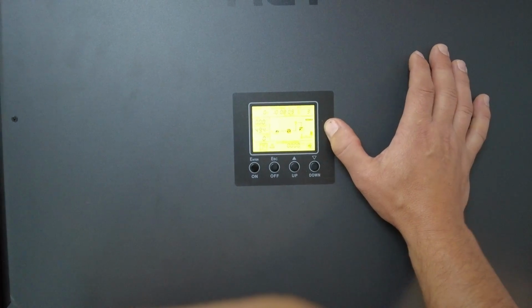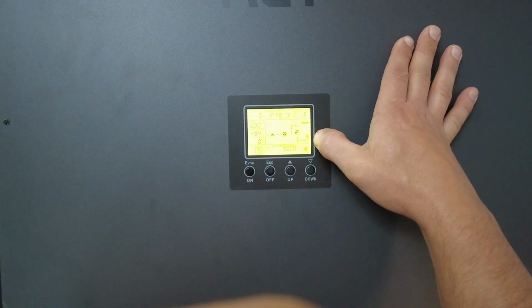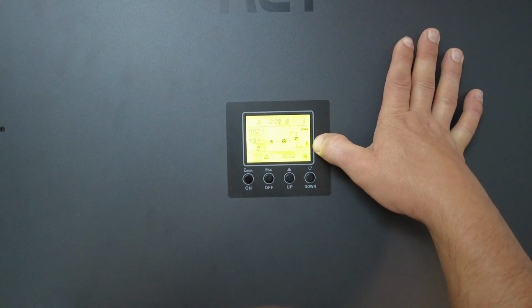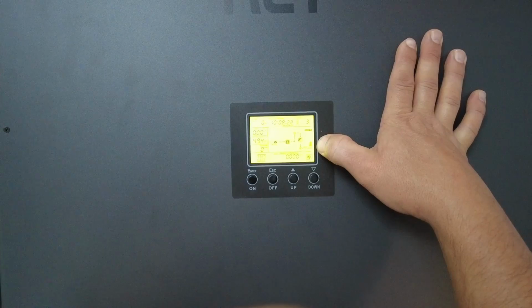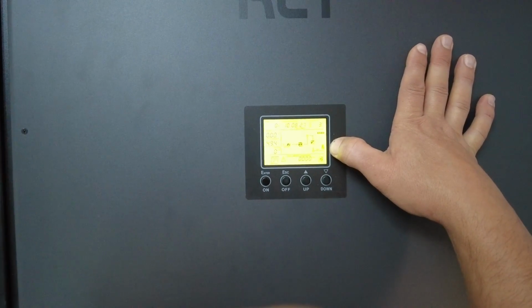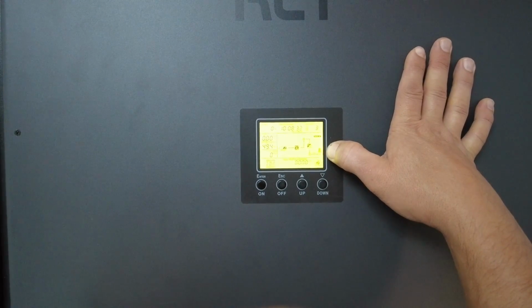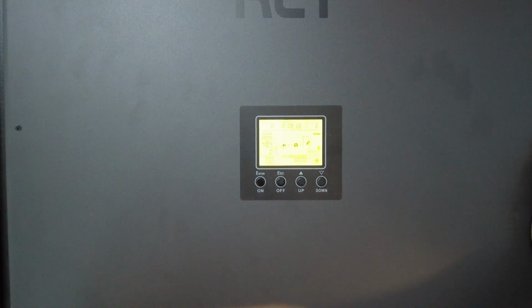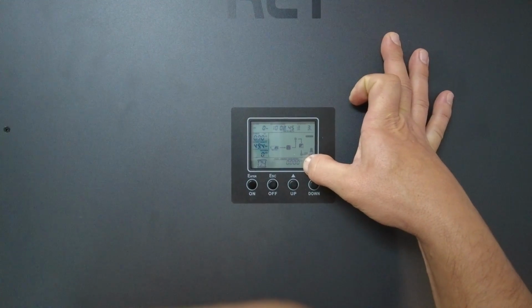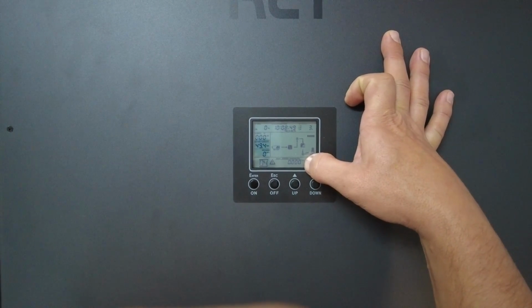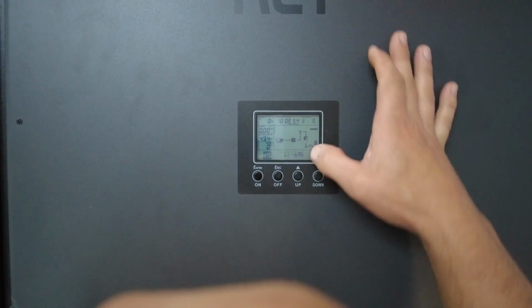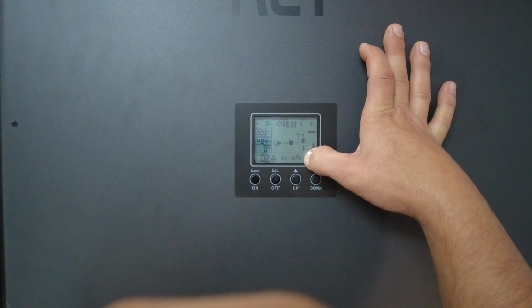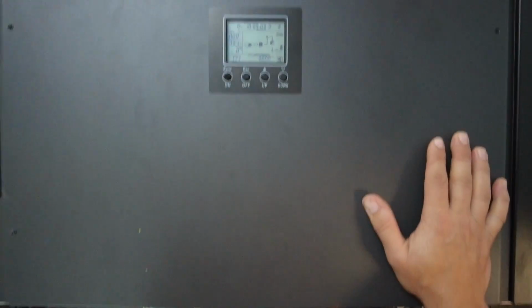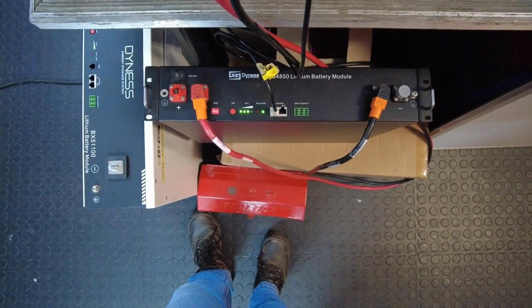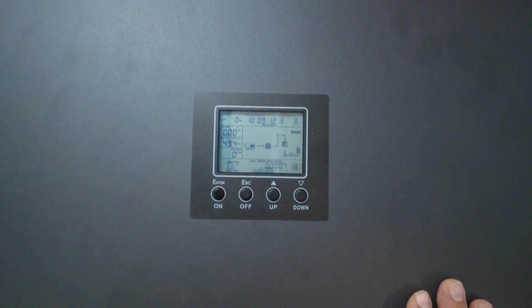Okay, the inverter just started up. From the battery icon, it's pushing power through to the light bulb icon, which is your load. Just waiting for the backlight to die down. There we go. So you should be able to see better now. You should see something written at the bottom here saying battery LI or LI BAT. That is your indication that BMS communication is established, which you can see just now. LI BAT. That is proof that you have BMS communication from the inverter to the battery connected. It is up and running and working well. Thank you very much.